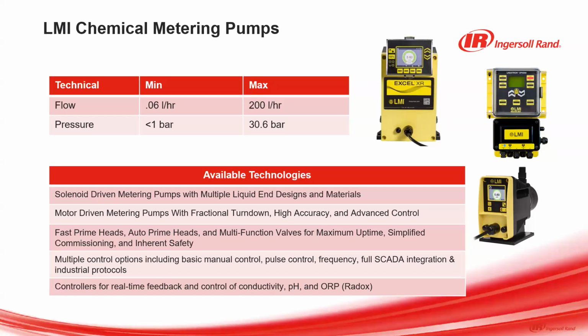In addition, in-process pumps for the digesters are required to balance chemistry in the anaerobic digesters and efficiently work through that process. So some of the available technologies that we have and applications that we can go into include solenoid and motor-driven pumps. These have specially designed heads, which are fast prime and auto prime, as well as multifunction valves for maximizing the uptime of the pumps, minimizing the requirement for maintenance people to be working on the pumps. It makes setup and commissioning and running, as well as maintaining these pumps, quick and efficient, and they're also inherently safe. So a solenoid pump and also our motor-driven pumps, in any case of overpressure or chemistry issues, especially if linked to a controller or the SCADA system being used in process, are going to be able to be fully controlled and safe.